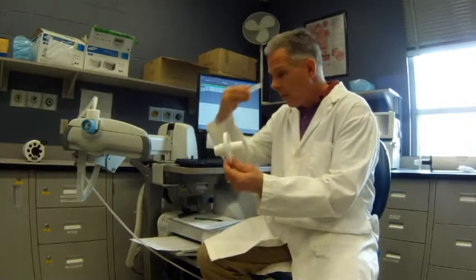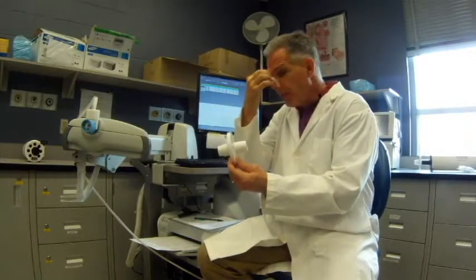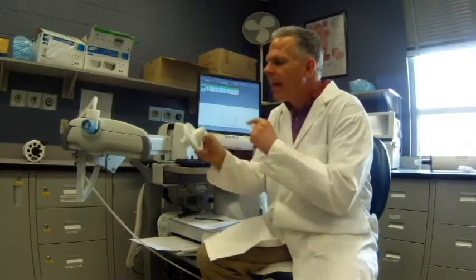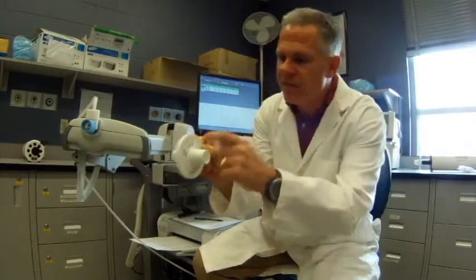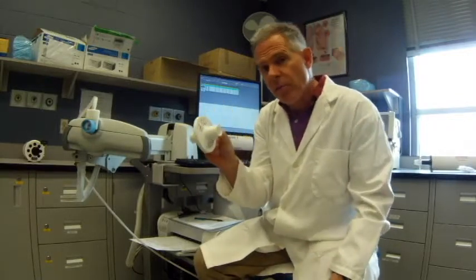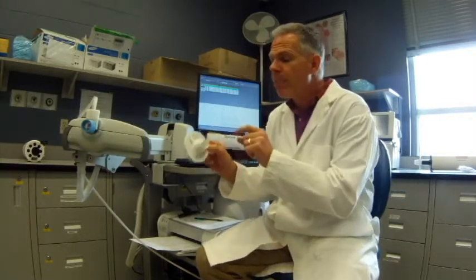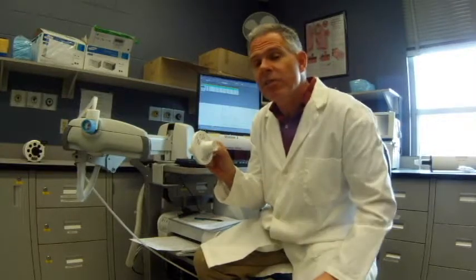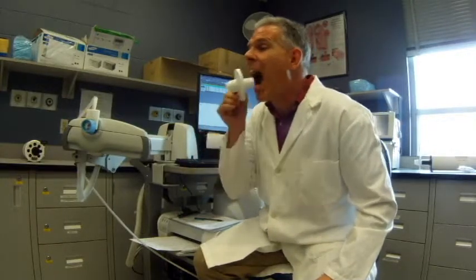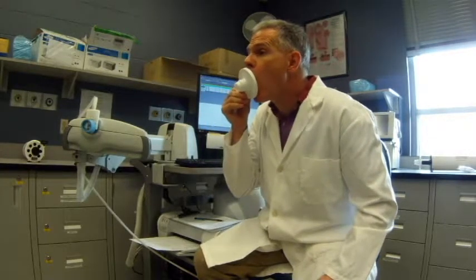So it's important to get a good seal. We're going to put on our nose clips, and they'll be wearing the nose clips for the test. We want to get our teeth on the outside of this filter and get a good seal around that with their lips. Now, if they're having problems doing that for some reason, you can use other kinds of mouthpieces that may help a little bit. But it's really important that they understand not to block the airway with their tongue. So don't block it with your tongue. Keep that clear. Keep your teeth on the outside and get a good seal like this with your filter, so you can breathe clearly and effectively through that. That's really important for our test.